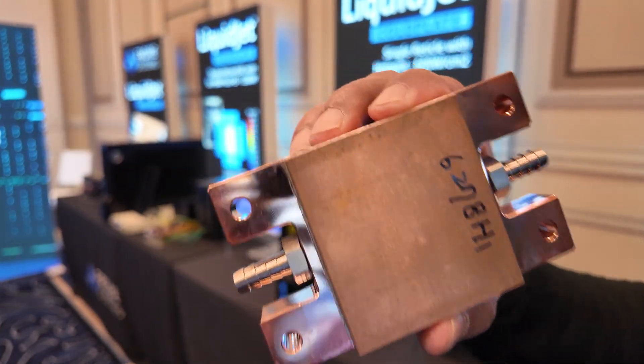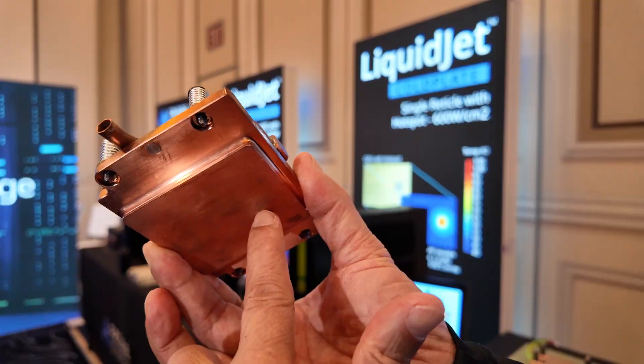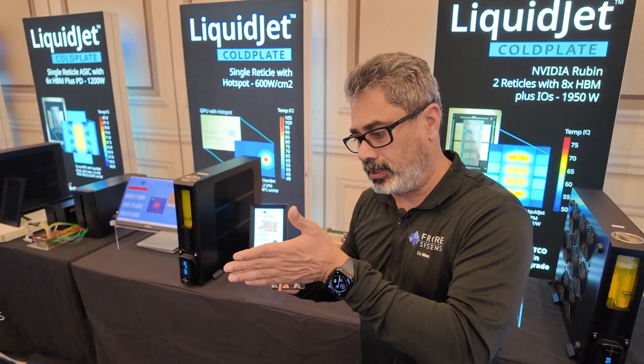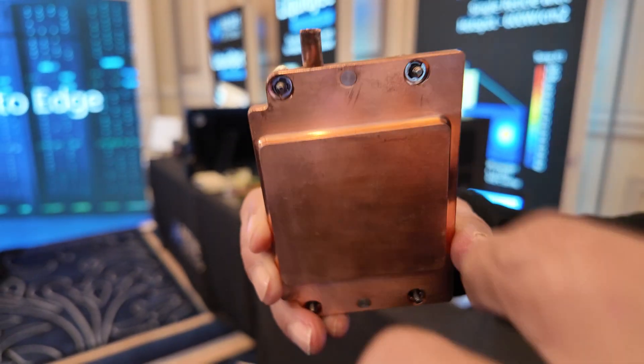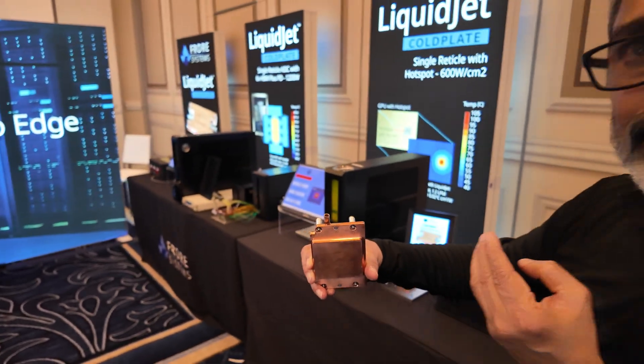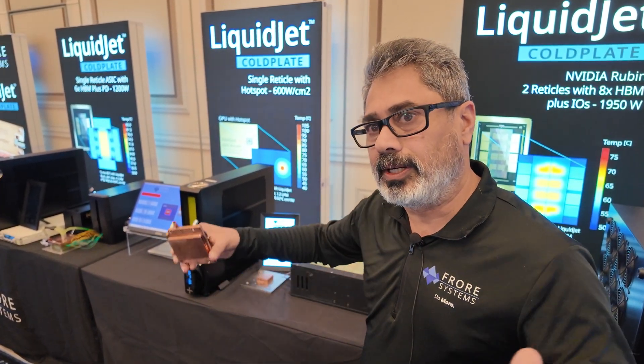What is the design? What do you do that's special here? Let me contrast it first with what the skive cold plates do. In the skive cold plates, they also have this base in which the skive structures are. Skiving is essentially a manufacturing process where the metal is cut or shaved and bent over, and a series of long channels are made. The length of the channel goes all the way across, and the fluid that enters has to travel at least 20 to 25 millimeters in the channel. The heat transfer is always higher as the flow enters the cold plate, but as it moves forward it heats up, and that heating up reduces the thermal performance. So you have a performance which has a large gradient.